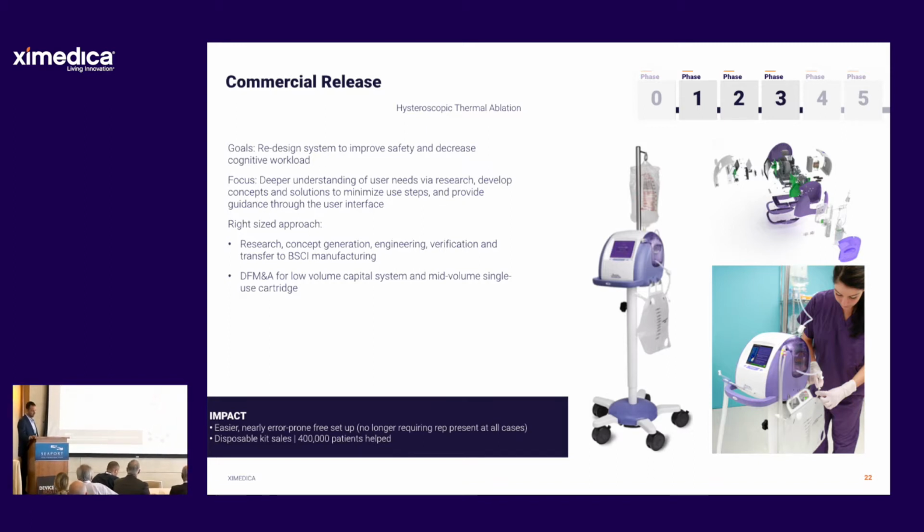And complexity. There's about 26 feet of tubing involved in the disposable part of the device. So that obviously contributed to complexity, cost, risk, and cleaning. They approached us with a pretty clear-cut engagement in this case, which was to develop a second-generation device addressing all those needs while minimally impacting their existing 510(k). Ideally, a letter to file would have been the best situation, without having to put a lot of effort into resubmitting for the regulatory approach.